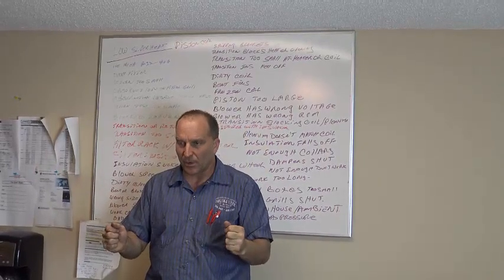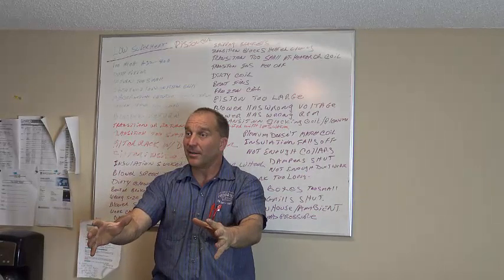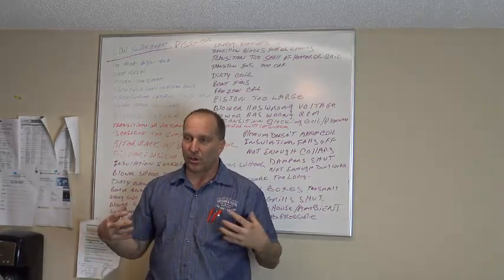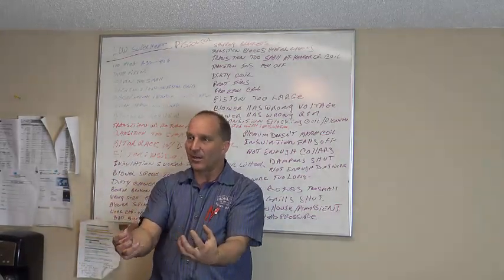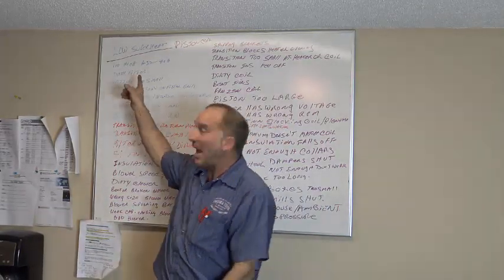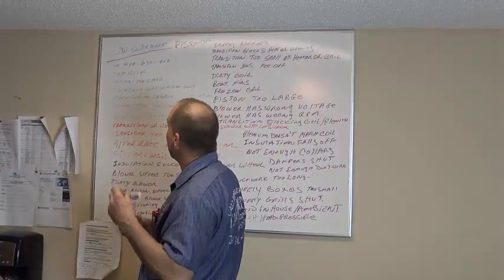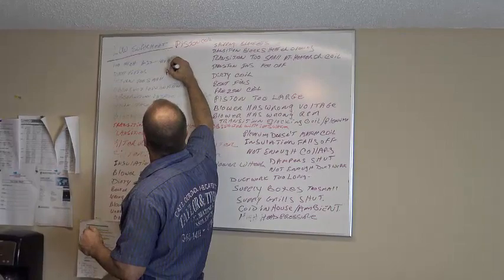When you stick that filter in that filter rack, it sucks inside there. When that happens, you're restricting airflow through that system. So that's going to cause a low superheat. So add your allergy-free filters in here, because that is definitely a problem. We see that a lot.